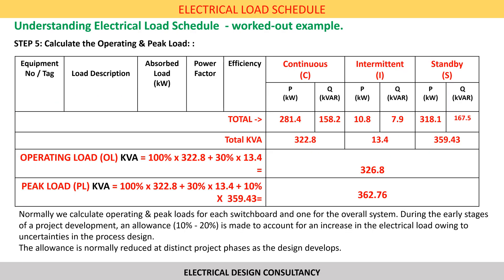Based on the formula discussed, we can now calculate the operating and peak loads. In our example, the operating load works out to 326.8 kVA and the peak load works out to 362.76 kVA. We normally calculate the operating and peak loads for each switchboard and one for the overall system. During the early stages of project development, an allowance of 10 to 20% is made to account for an increase in electrical load, to take care of uncertainties in the process design. This allowance is normally reduced at distinct project phases as the design develops and the details of the electrical loads are crystallized.